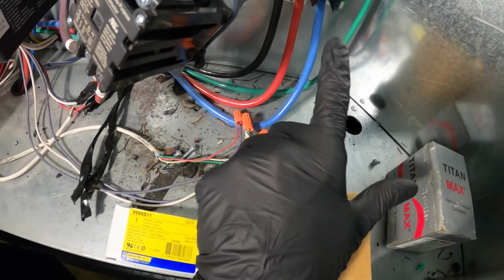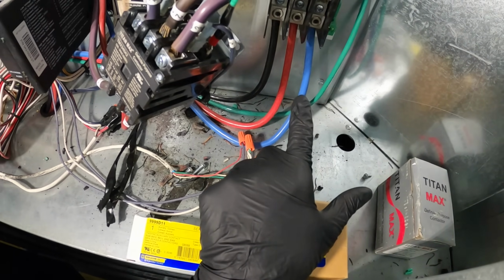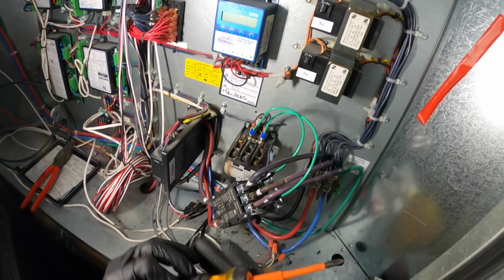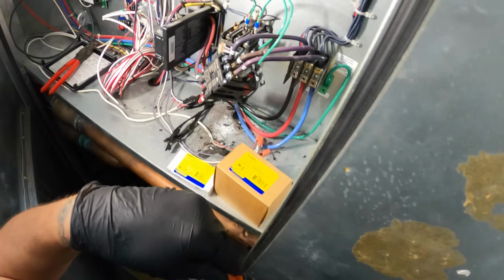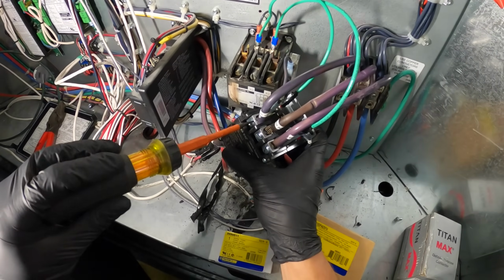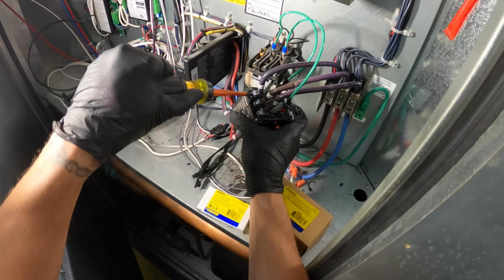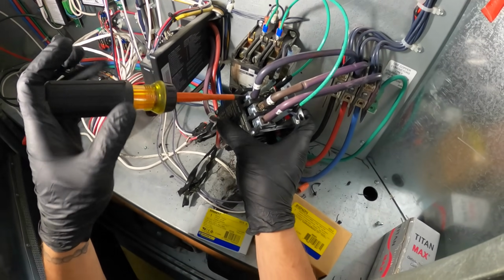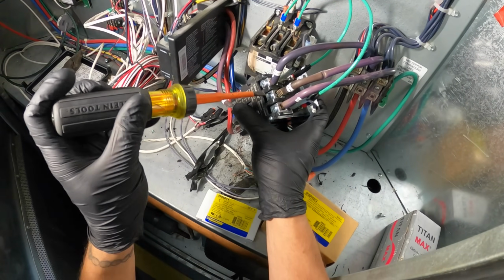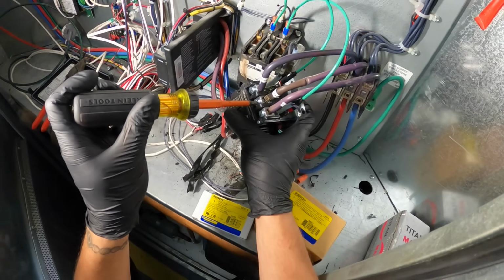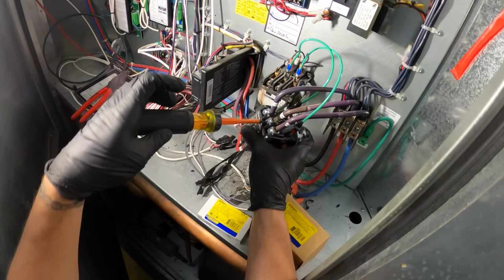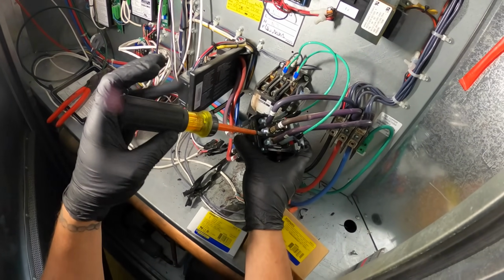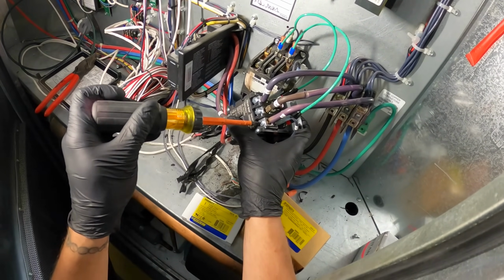All right, so line voltage comes from here. This is our line voltage terminal block. Power is off. We left it off the other day because you don't want to run this with the undersized contactor. It's good for 40 amps. And I remember it was running at like 32 or 33 amps, so we're kind of cutting it close. You don't want to burn that thing out either.